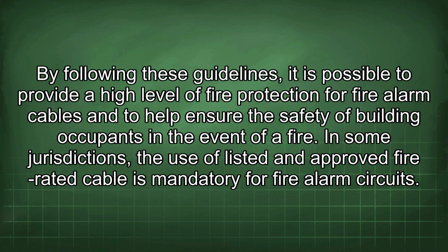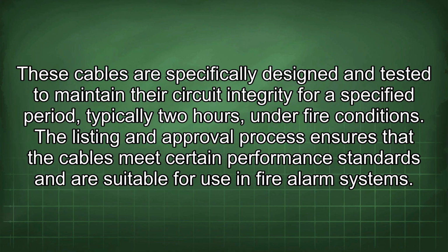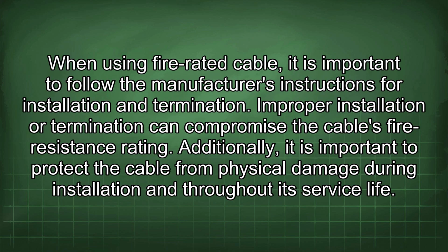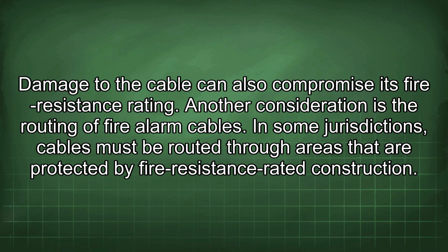In some jurisdictions, the use of listed and approved fire-rated cable is mandatory for fire alarm circuits. These cables are specifically designed and tested to maintain their circuit integrity for a specified period, typically 2 hours, under fire conditions. The listing and approval process ensures that the cables meet certain performance standards and are suitable for use in fire alarm systems. When using fire-rated cable, it is important to follow the manufacturer's instructions for installation and termination. Improper installation or termination can compromise the cable's fire resistance rating. Additionally, it is important to protect the cable from physical damage during installation and throughout its service life. Damage to the cable can also compromise its fire resistance rating.